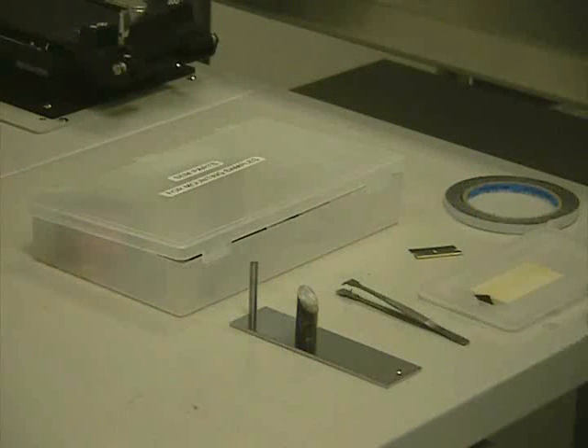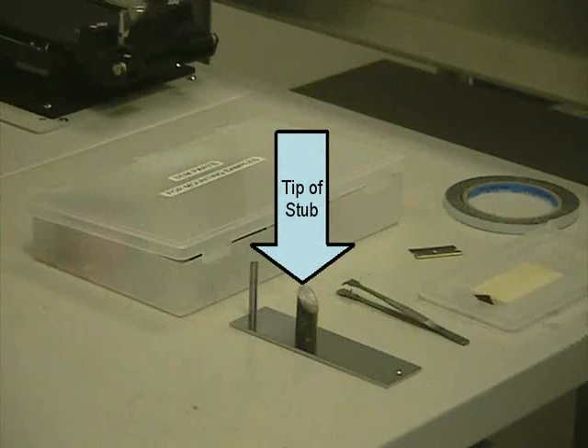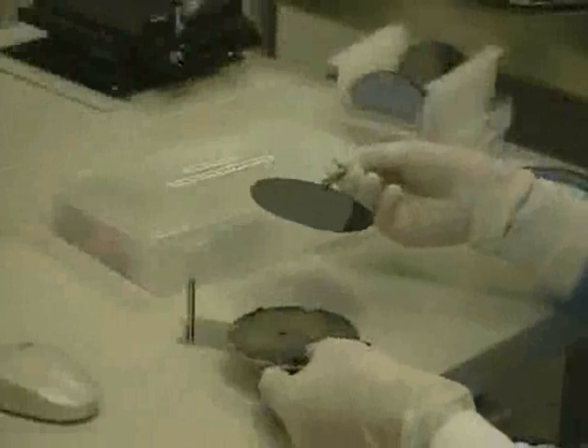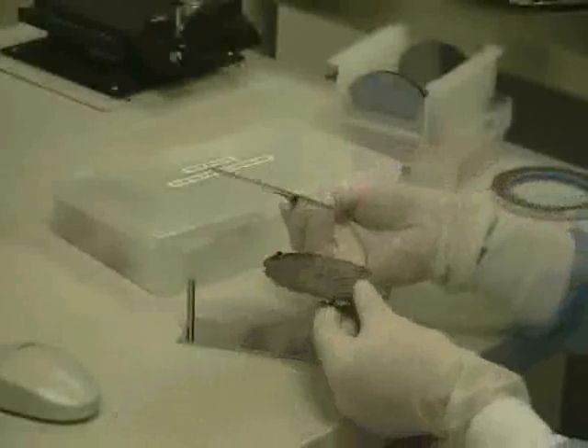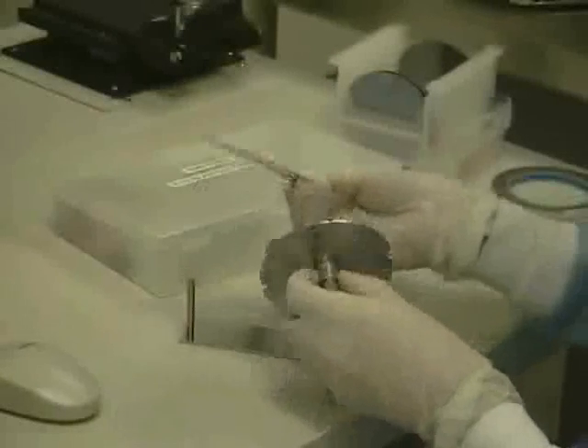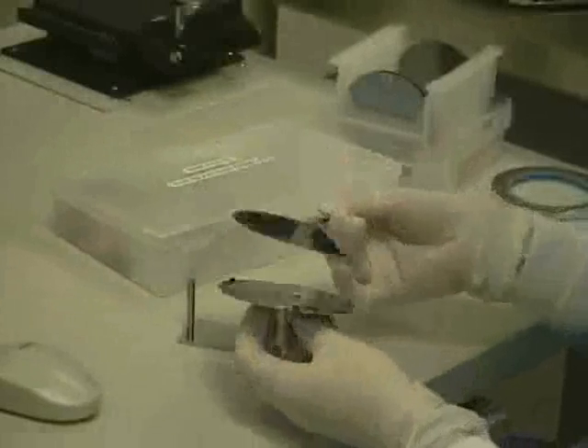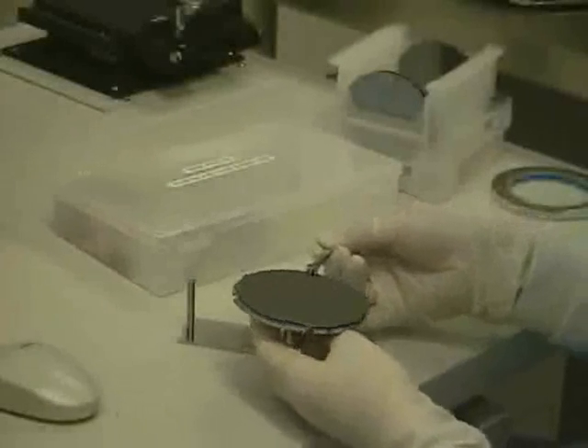Please use the trash cans that are readily available throughout the clean room. If we want to look at the edge of a sample, we use a stub with an angled top. We place a piece of tape on the top and mount our sample so that the edge we want to look at is on the tip of the stub. If we want to mount an entire 4-inch wafer, we use a large mounting stub. Mount the sample using the tape the same way in which we mounted the other samples.